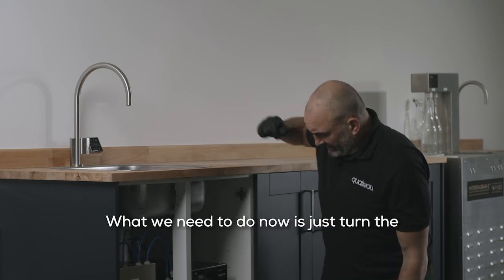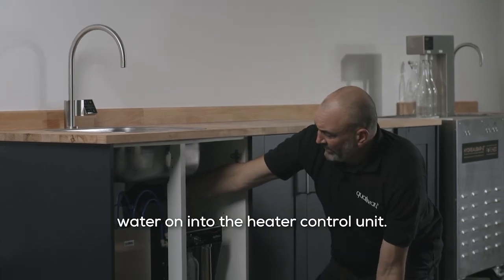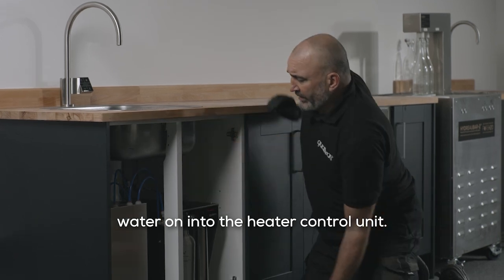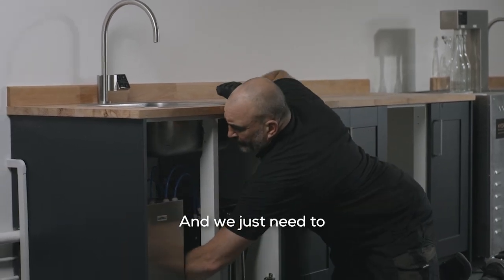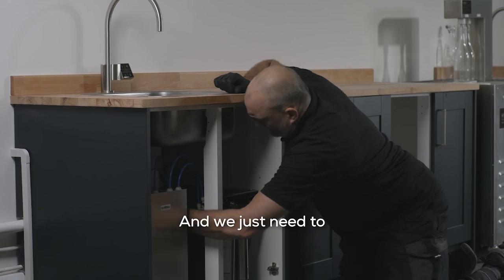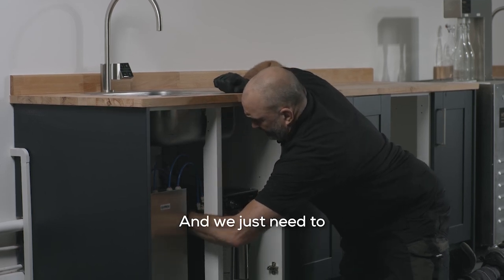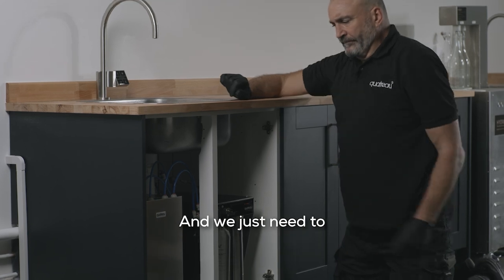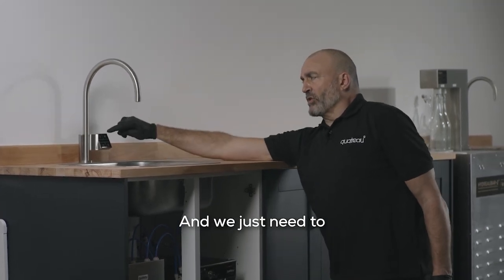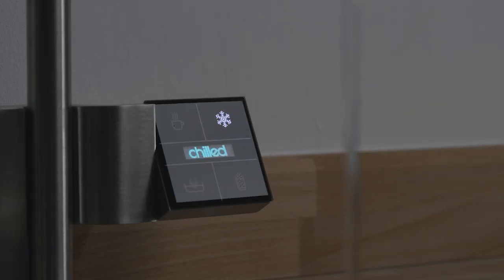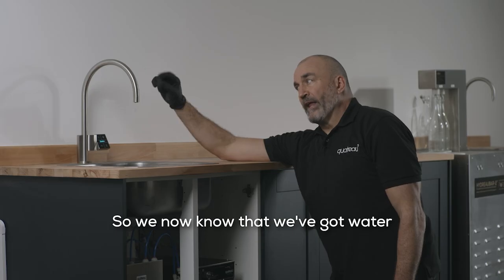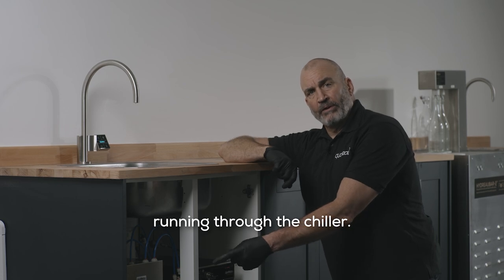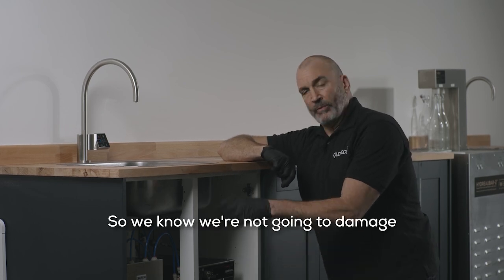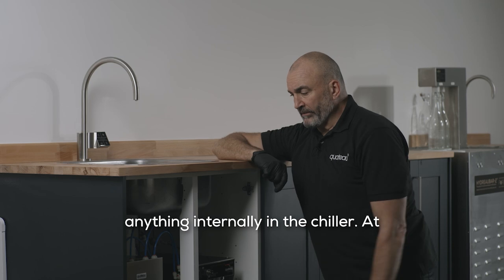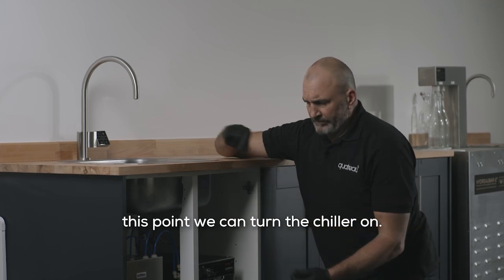What we need to do now is just turn the water on into the heater control unit. And we just need to go up to the Quatreau TouchTap screen and press the chilled function icon. So we now know that we've got water running through the chiller, so we know we're not going to damage anything internally in the chiller. At this point, we can turn the chiller on.